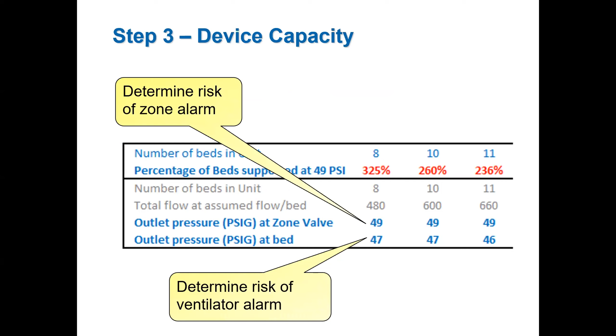So how do you make these calculations? Well, first of all, if you find that you have a pressure drop problem, or you have a flow capacity limitation, and you can't handle 60 liters a minute at the bedside, that's the worst case. Well, then you're going to have to scale back. Now the question is, scale back to what? So now you're going to have to ask the question of what are the different combinations of things that you're going to attach to the wall.